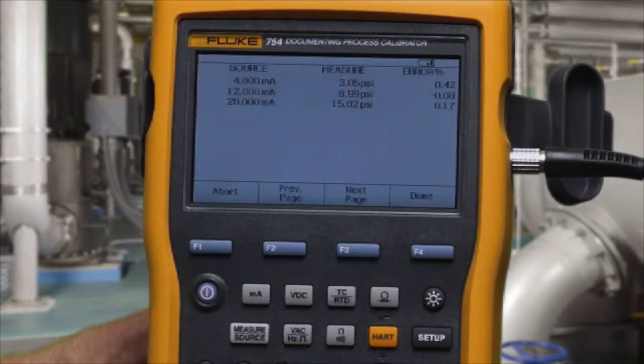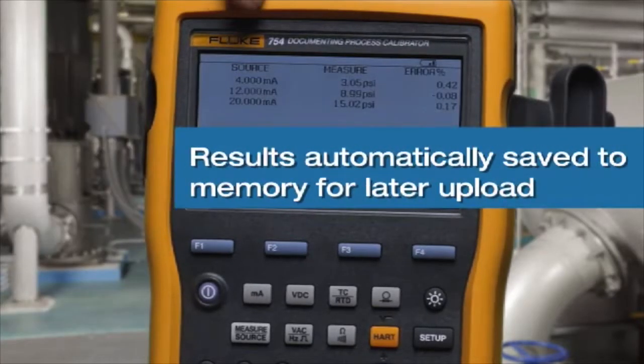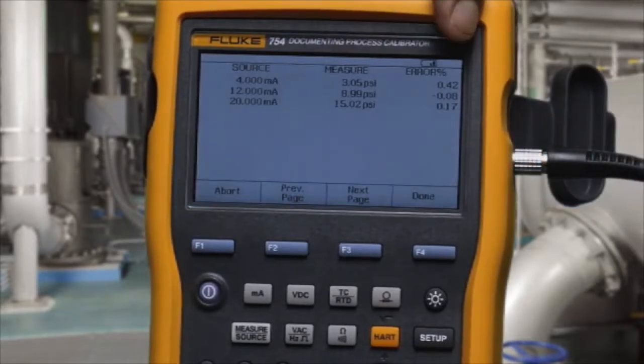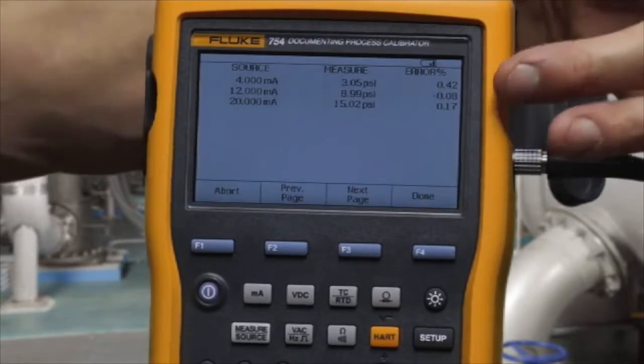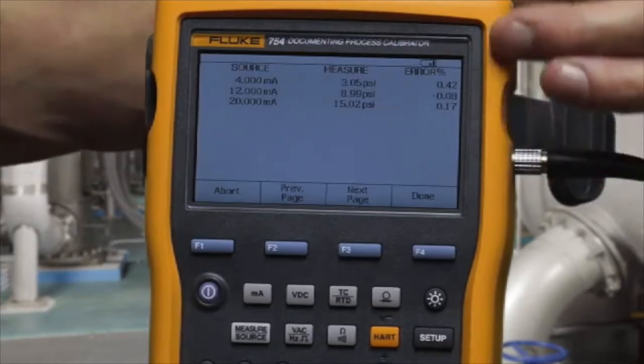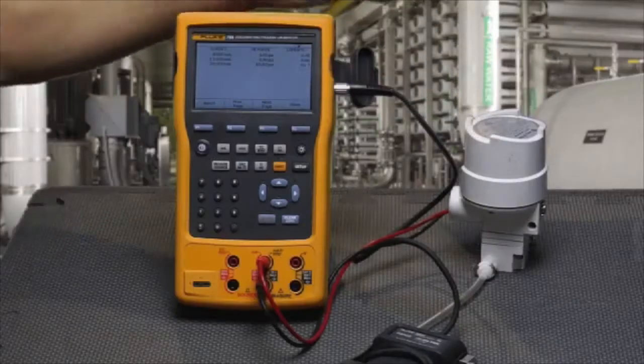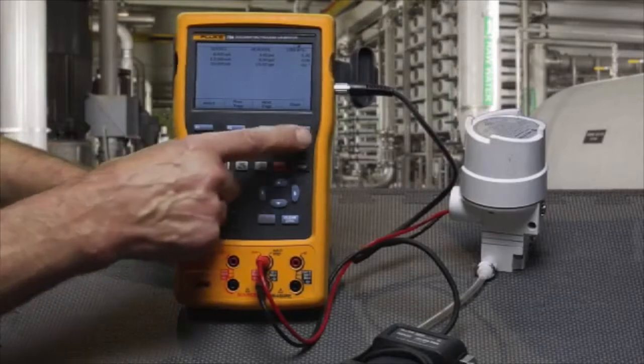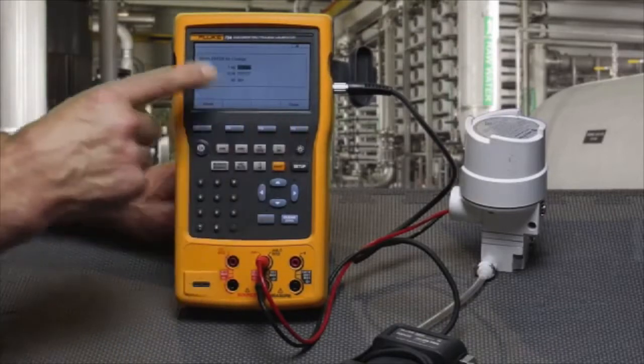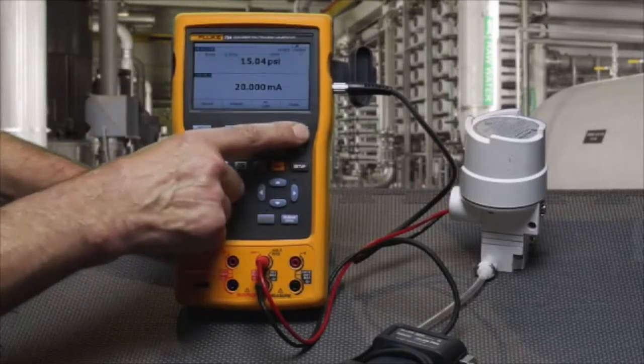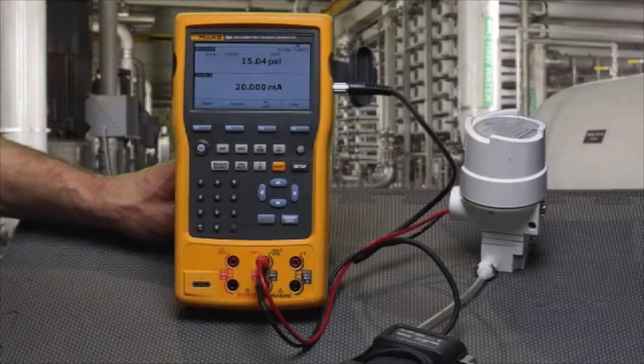When the test is complete, you get the recorded applied milliamp value, measured PSI, and error percent of span. All these errors are in green, indicating that this I2P passed this calibration test. And then done. Tag and serial number would manually be entered in. That is how you do a performance test on an I2P using the Fluke 754 documenting process calibrator.